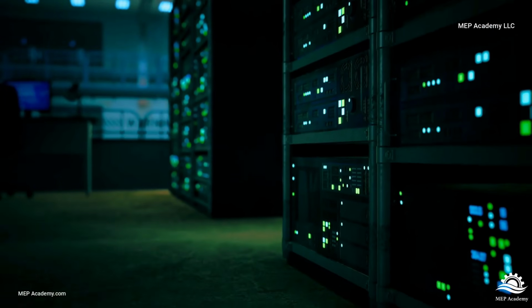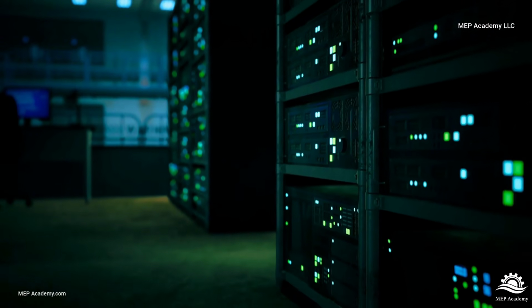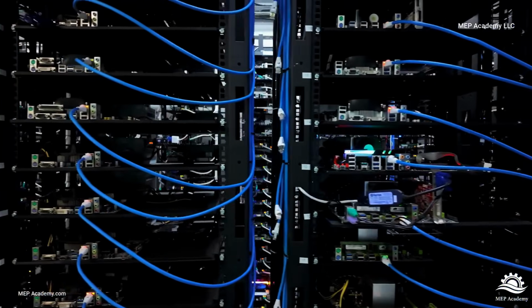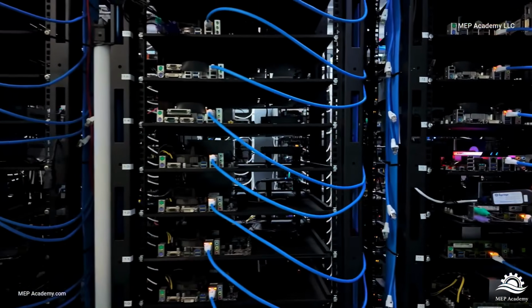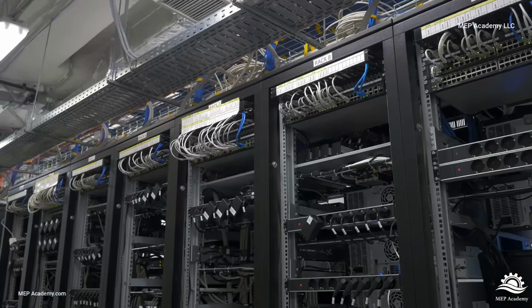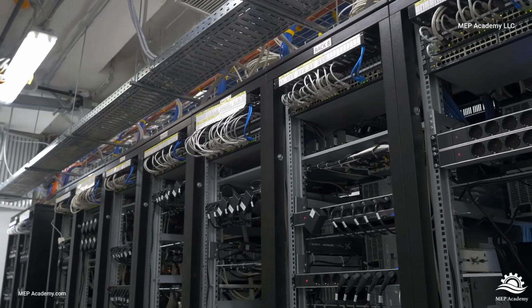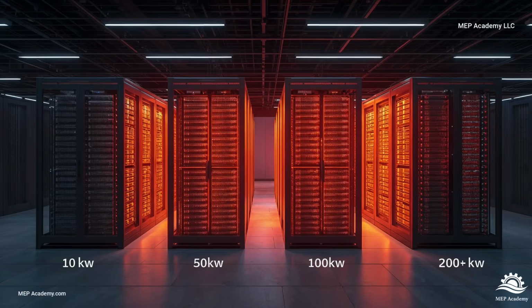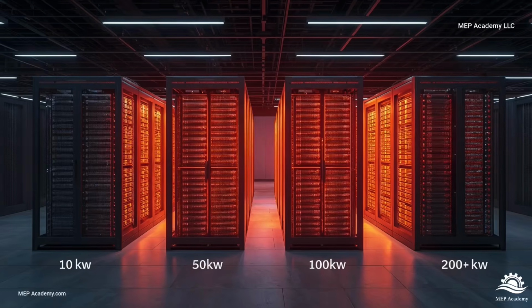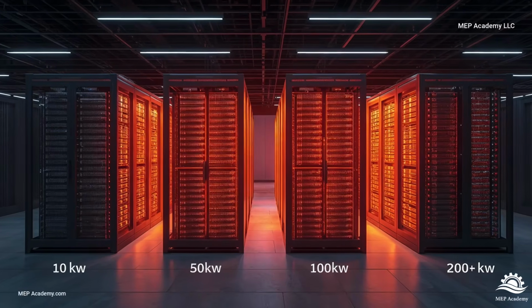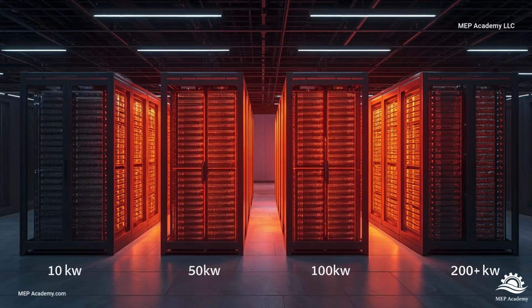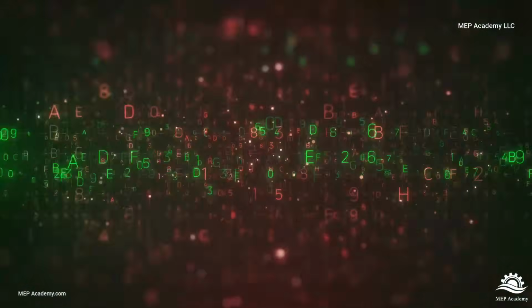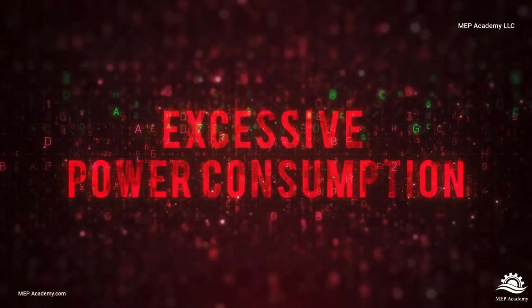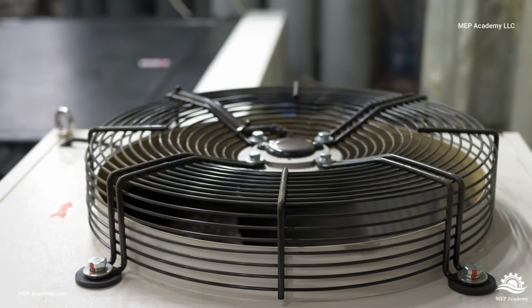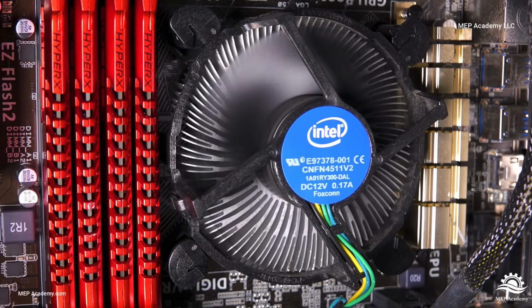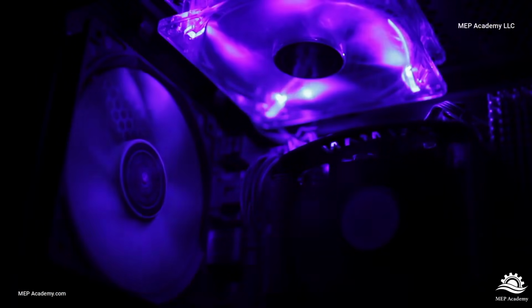Now imagine multiple AI servers installed within a single rack. Rack densities that once averaged 10 kilowatts are now reaching 50, 80, and even well over 100 kilowatts per rack. Some of the newest AI deployments are approaching 200 kilowatts and beyond. The challenge isn't supplying the power. The challenge is removing the heat. Because every watt of power consumed by a server eventually becomes heat that must be removed from the building. And that's where traditional air cooling begins to struggle.